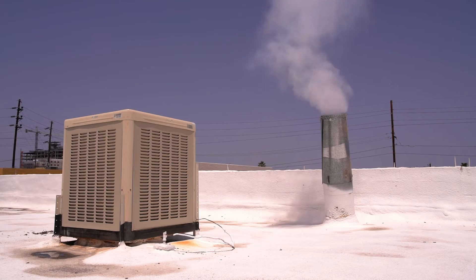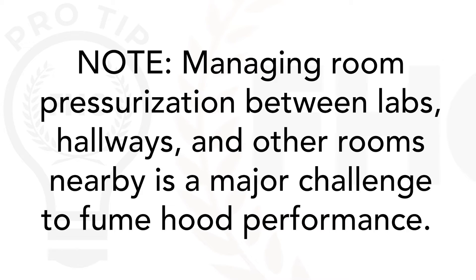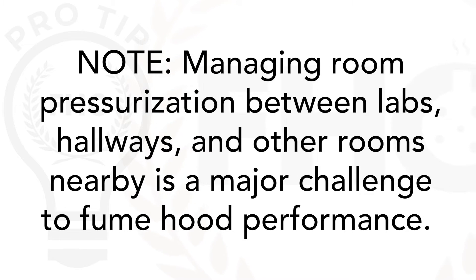Any imbalance can cause the direction of the flow to change. Managing the room pressurization is a real challenge to fume hood performance — pressure changes can reverse flow, which can result in unsafe conditions in the lab.